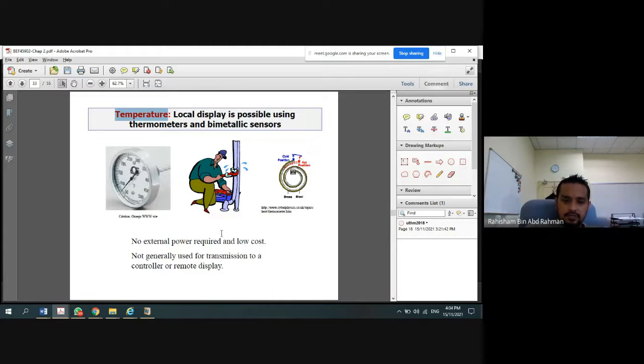Okay, there are several approaches as well, just like with the flow sensor, and some of them are like this one. A local display is possible using the thermometer and the bimetallic sensor. So as I explained before, why do we need a local display? We need to install the display at this point, although we already have the control room to know the temperature, etc. But when it comes to maintenance, sometimes we really need the sensor or the measurement on site, so that the maintenance can be done easily and effectively.